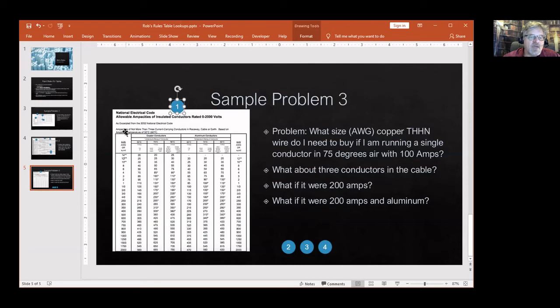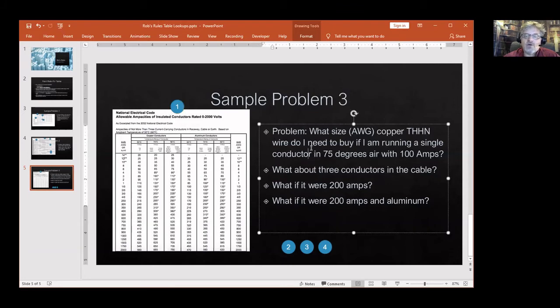Then down below it says ampacity is not more than three current carrying conductors in raceway, cable or earth. Whoa, three current carrying conductors. Do I have the right table? No I don't, because I ask about a single conductor, a single conductor in 75 degree air.